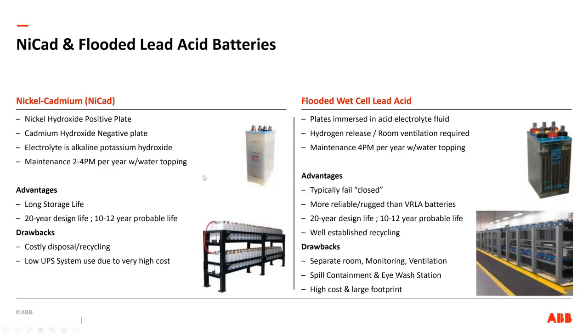So it's possible, all UPSs can work with nickel cadmium batteries, but there are some issues. There are some benefits with nickel cadmium. They have very long life and they are rugged, especially temperature wise. So I haven't seen them much in a traditional IT environment. I've seen them on UPSs in areas of the world, rugged environments where it was very hot, and at that time mostly when the alternative was a lead acid battery. Lead acid batteries generally do not handle high temperatures very well.